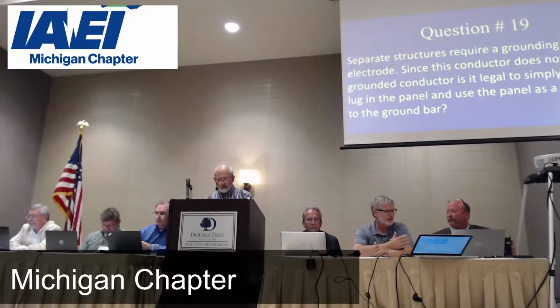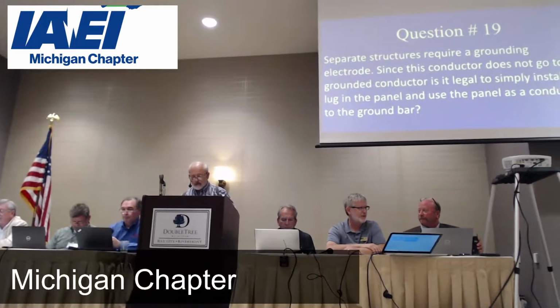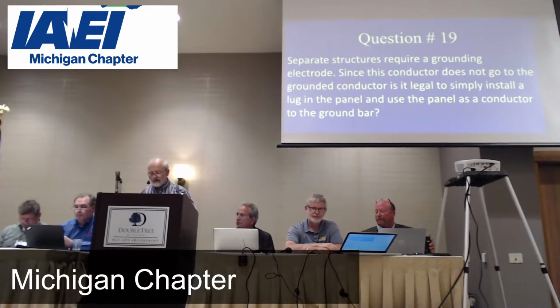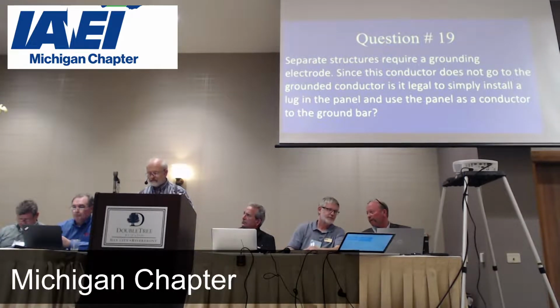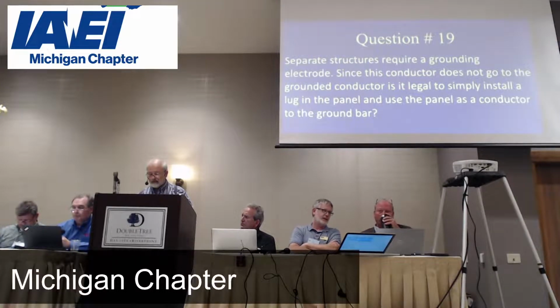Okay, question number 19, Tom. Separate structures require grounding electrode. Since the conductor does not go to the grounded conductor, is it legal to simply install a lug in the panel and use the panel as a conductor to the ground bar?